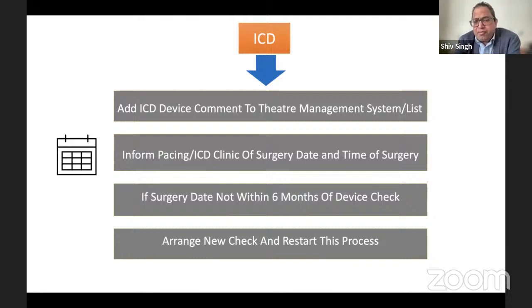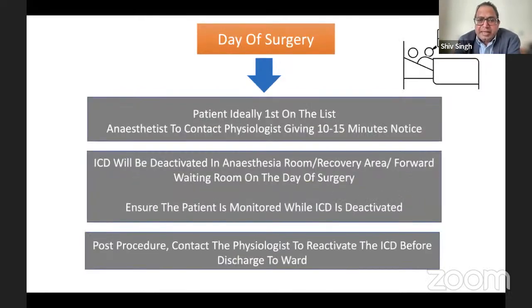The patient should be first on the list, the reason being that, for example, our cardiophysiologists only work from 9 to 4. So it's better to get the case done early in the morning, so that they can come and reset the whole thing, because the pacemakers need to be deactivated when the patient goes to the theater. Once the ICD has been deactivated, the patient needs to be monitored until the patient actually reaches the theater.